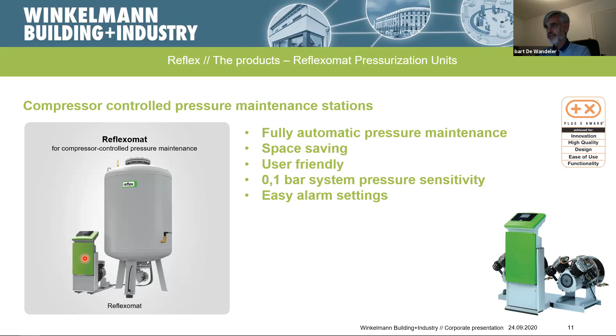So this is one of the big advantages of using these automatic systems. There's also an easy alarm setting, so the installer can monitor from a distance via remote control to his iPhone, iPad, or Android phone, or it can go to a BMS system in the building. It's a very easy setup, and we provide the most standard common Ethernet connections for alarm settings - like Profibus, Modbus, Ethernet, BACnet - all available in the Reflex systems.